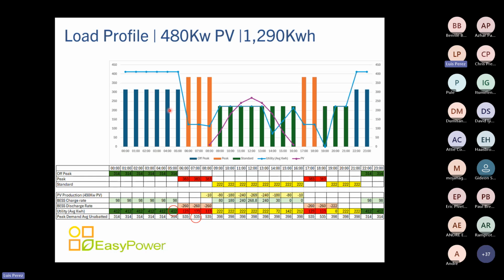So net, even if we're increasing our demand at night by charging this battery at 98 kilowatts, the end result is that we are shaving about 120 kVA of real demand from this customer, which we can shave whether the weather is good or bad. And why is that? Because we are reducing the peak demand during the time that they're having the real load peak. So for as long as the PCS and BSS are working, there will be a guaranteed drop in demand.